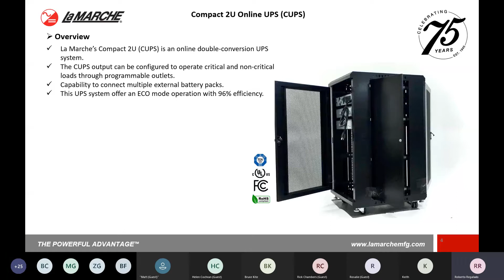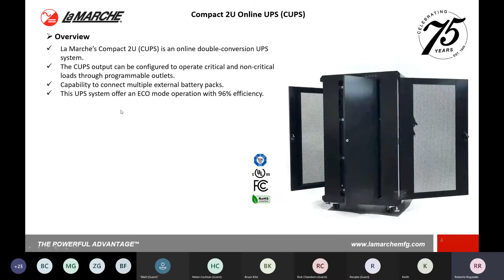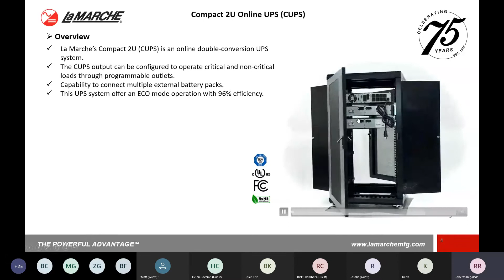Some of the connections on the UPS as far as the output are through programmable outlets. And going forward, you will see that some of those outlets do have some non-critical positions as far as the terminal strip that you can see on the back of the module. And then you can designate some of those time durations or your priorities on the output side. The other thing that you see here is this battery pack with this power module, and you can see different types of battery packs that you can mount with it. We do have a couple of part numbers set up already for external battery packs that can be paralleled to allow for a designated amount of runtime depending on your total power capacity. Efficiency is up to 96%, and that's with the eco mode. As far as AC power or battery powered efficiencies, we're probably ranging around 90% efficiency.